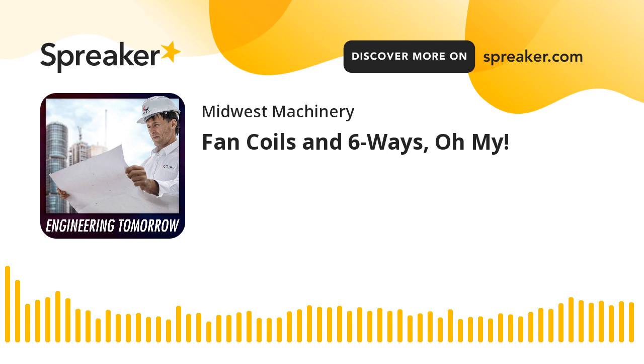What is interesting also is that if you design a building, sometimes people use an N+1 where they'll use 2 chillers as opposed to, say, 1. So if that one chiller needed to go offline to do cleaning or whatever happened to it, normal maintenance, your whole building wouldn't be down. You'd be able to go with the backup system, and the same with the boiler.